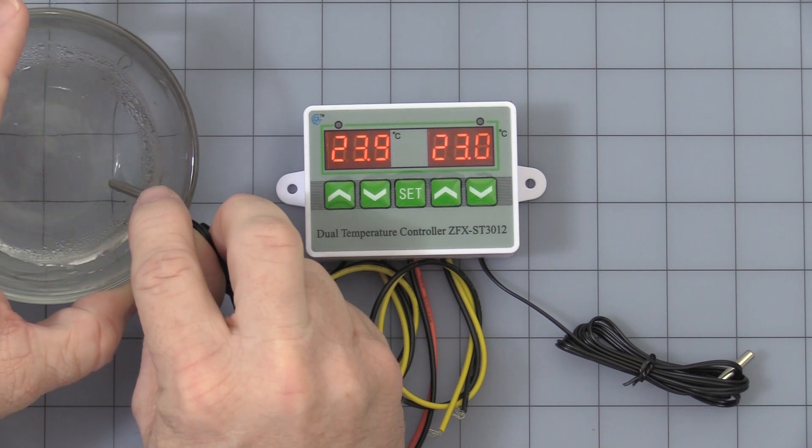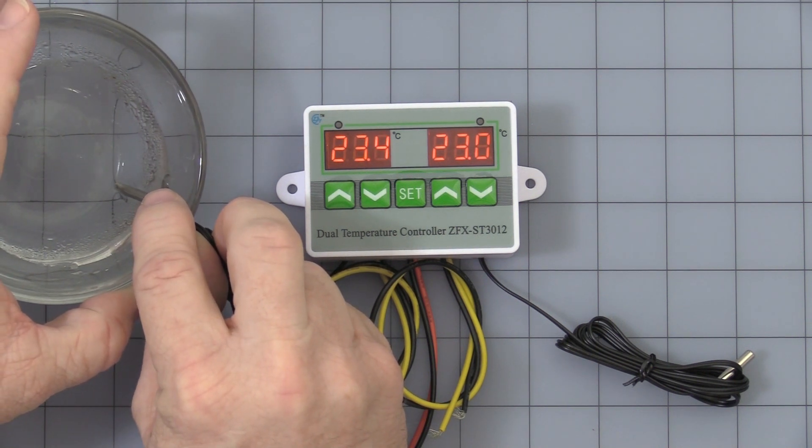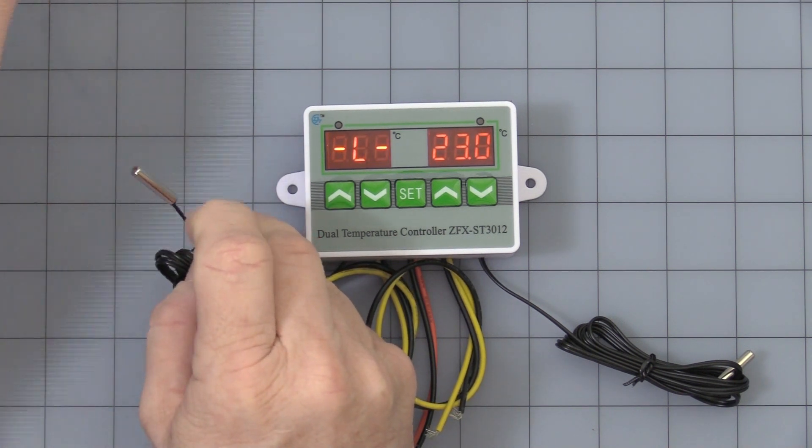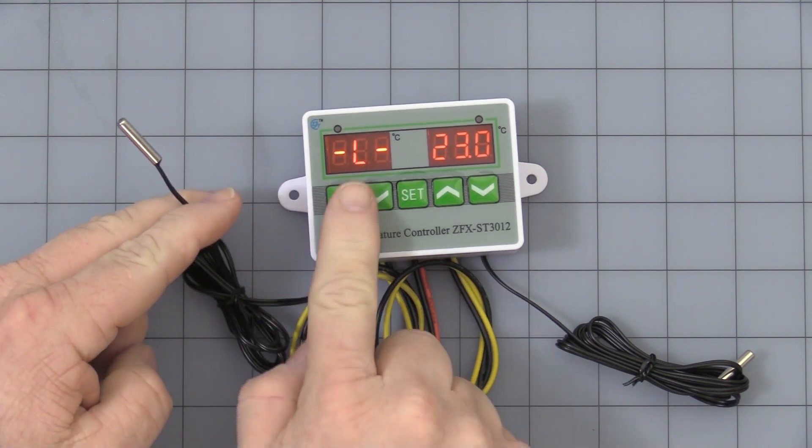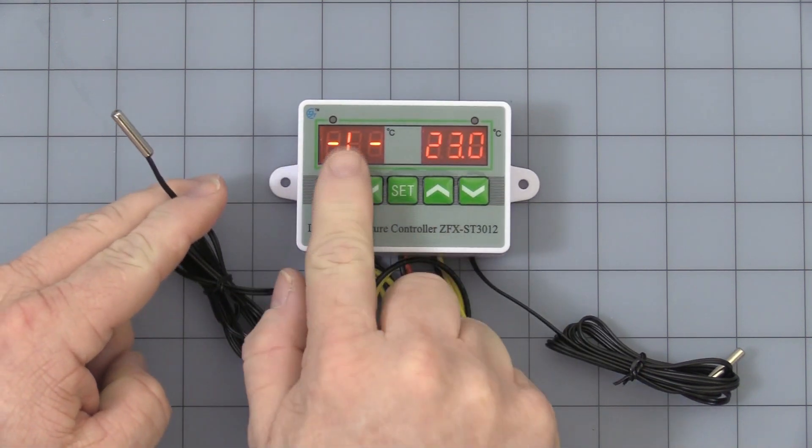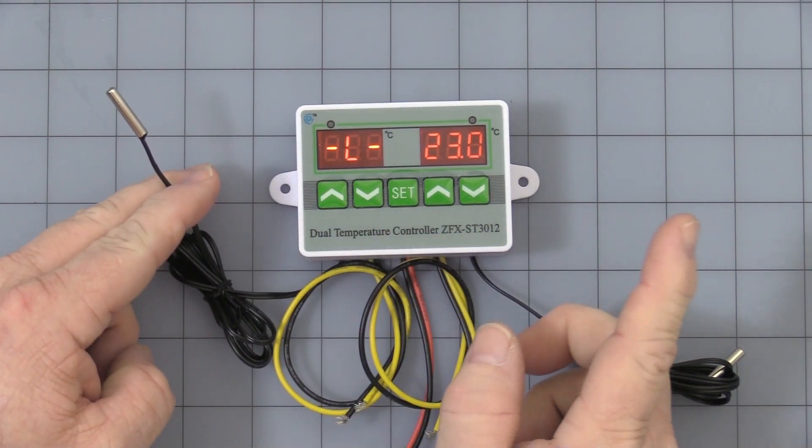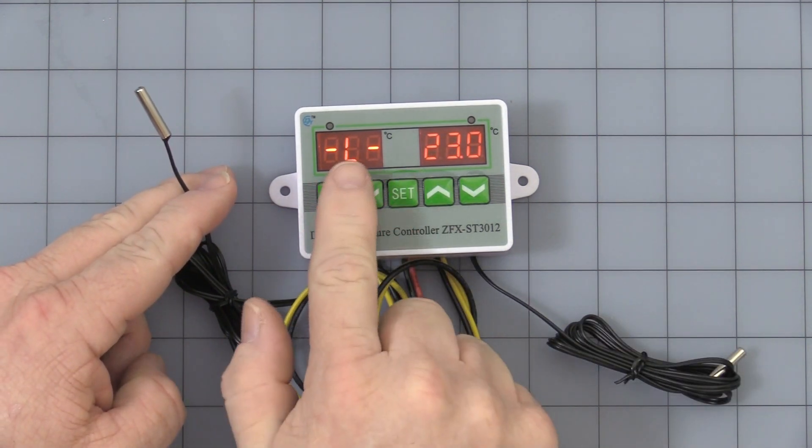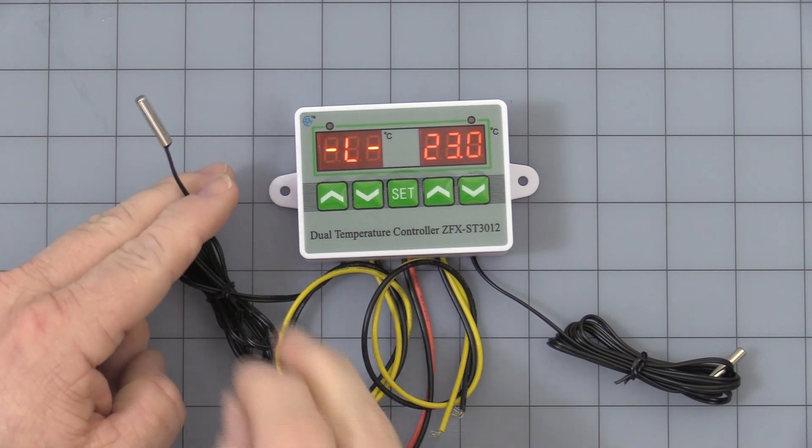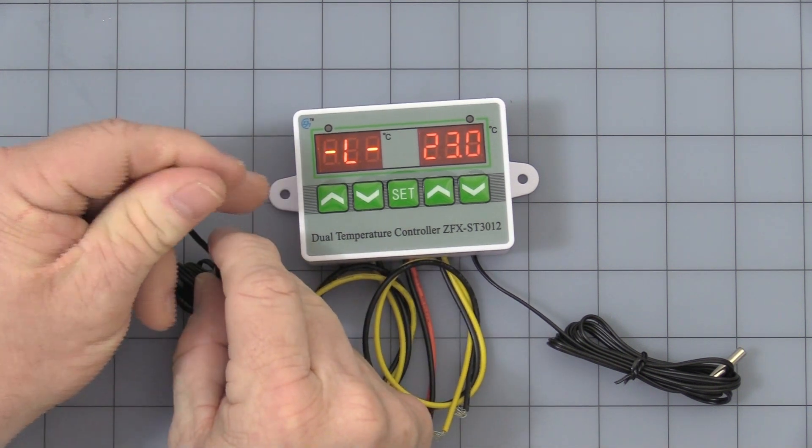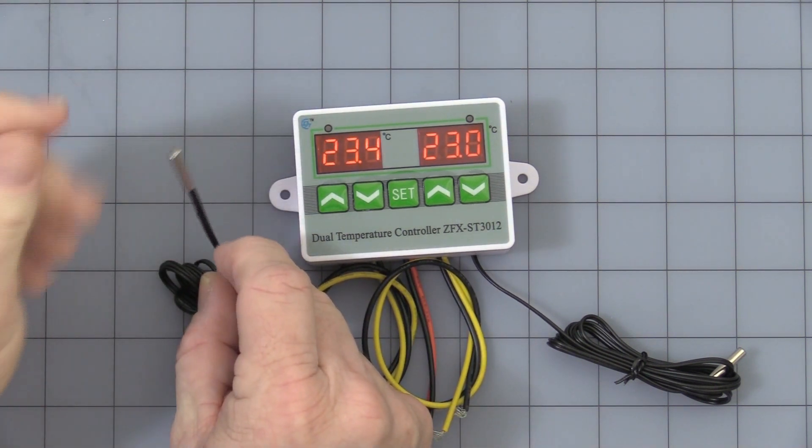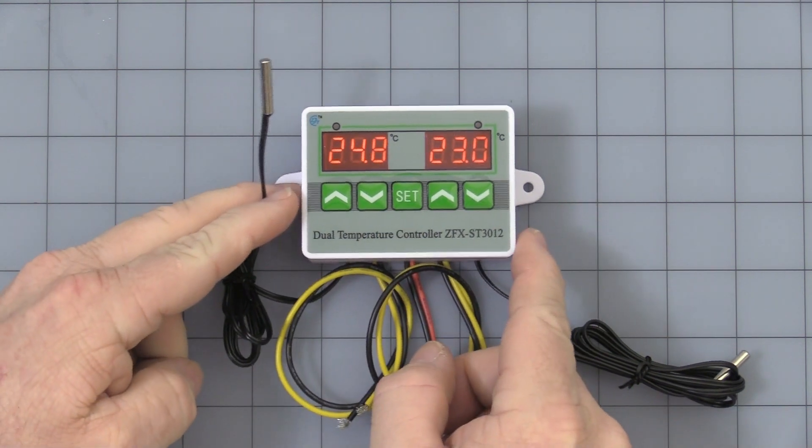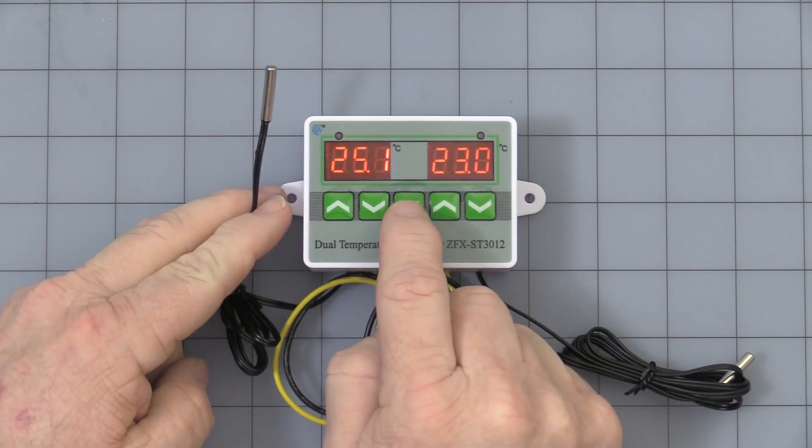Now to show you what the low temperature alarm does, let's get it down to that set point. It will start flashing, start beeping and you see it just said L. You should be able to hit the set button and stop the alarm, but it will always just show the L until the temperature rises above that low level alarm point. There you go. Then it starts displaying ambient temperature.